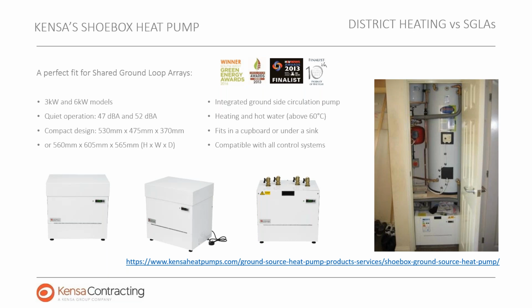It comes in 2 sizes, 3 kilowatt and 6 kilowatt. Obviously, those sizes are designated when a full design and heat loss calculation is done on the property. It's very quiet in operation, 47 and 52 dBA respectively. Once they are inside a cupboard, it'll be difficult to hear the unit running, and actually the energy efficiencies that usually are taking place by the owner mean that the unit is not running 24/7 at all. It's only running at certain times when heating and hot water requirements are called for.